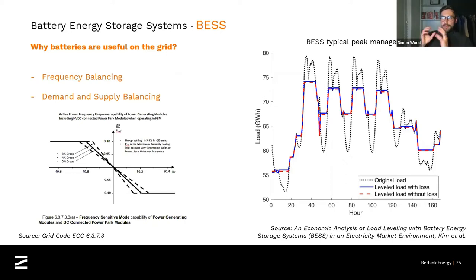But ultimately, batteries are useful not just as a way to balance supply and demand, but as a stabilization mechanism for National Grid or the distribution operators to be able to maintain the network. That has become increasingly important in recent years as more renewables have come onto the system. We've got a more intermittent energy system, and it's become decentralized. Some of you may be aware of the blackouts that we had a few years ago. That was an issue with grid frequency.